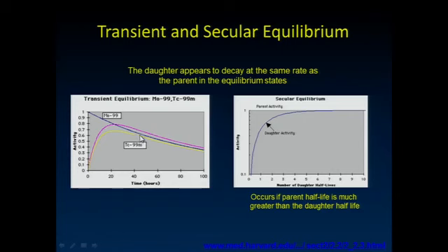So it's really nice to set up. The ratio of half-lives between molybdenum and technetium are such that you end up in this transient equilibrium that reaches its maximum right around 24 hours, which is really convenient for what we do, where each morning we'd want to elute the generator and start our imaging for the day, if you will.